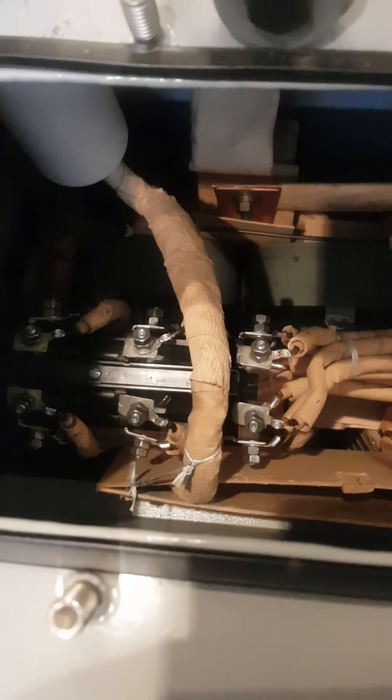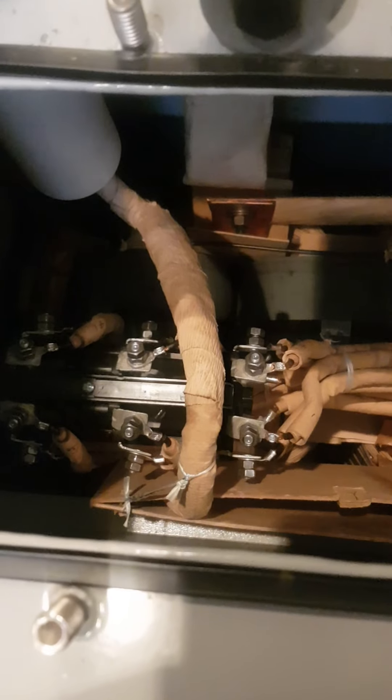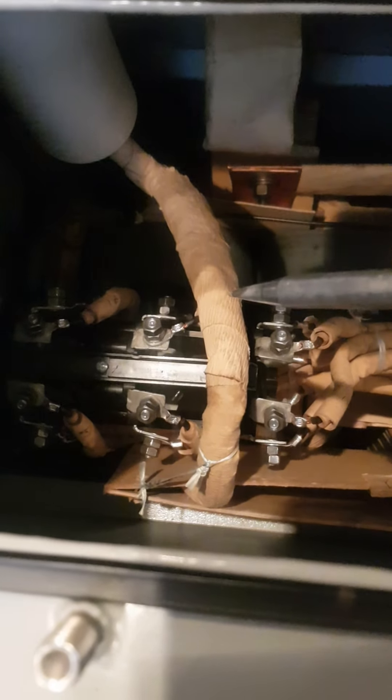From the windings, you will have the terminals of the high voltage and low voltage windings coming out, and these need to be connected to the conductor coming out of the transformer. So how do we take the high voltage connection from the winding to the outside world? We do that through the bushing.